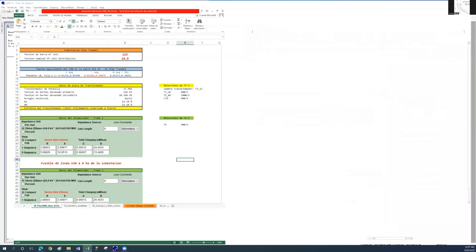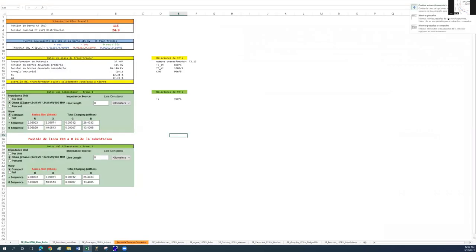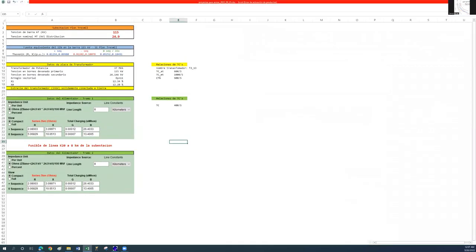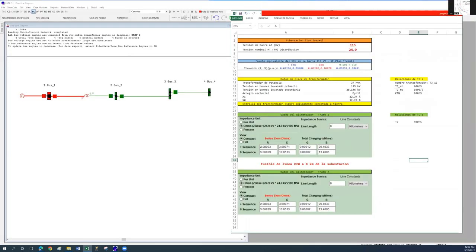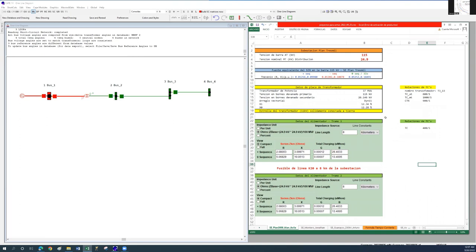On the high voltage side of the transformer, I will place a set of three 600 to 5 CTs. On the transformer neutral, we will place a single 900 to 5 CT. While on the feeder, we will place a 400 to 5 CT.